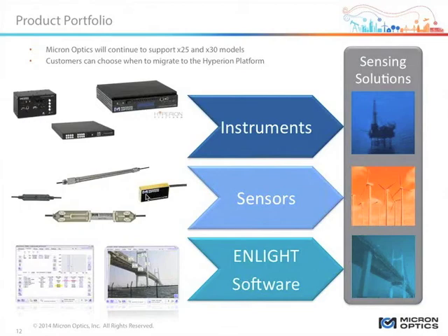range. By having the single board design, all of our heat generating components are placed on the same side and directly conductively cooled through a heat sink. And so what that does is it puts all of our heat generating components in a very controlled environment that can only extend the life of those components and lead to long-term reliability in the field.